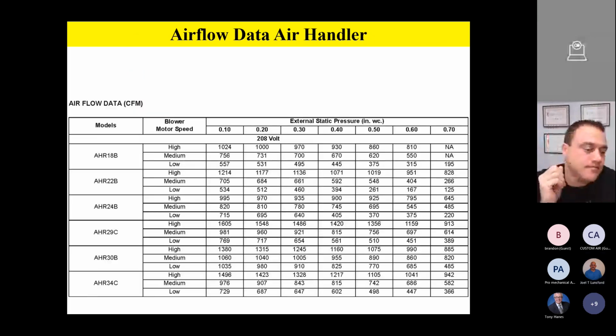Okay. So let's take a look at some airflow charts for an air handler. So this particular air handler here, we know we've got a lot of capacitor style air handlers out there yet, AHR air handlers. This is a very, very common air handler. And by the way, every manufacturer should give you some sort of airflow chart. This happens to be our AHR air handler, which is a capacitor style air handler. We know there's a lot of them out there yet. So the way this chart works is this.